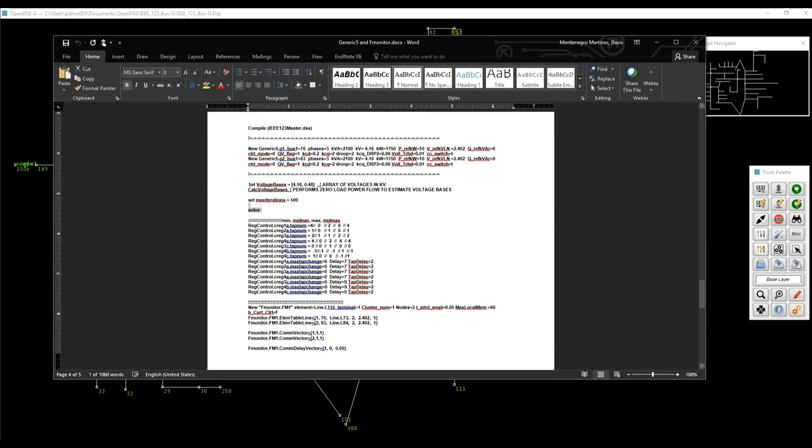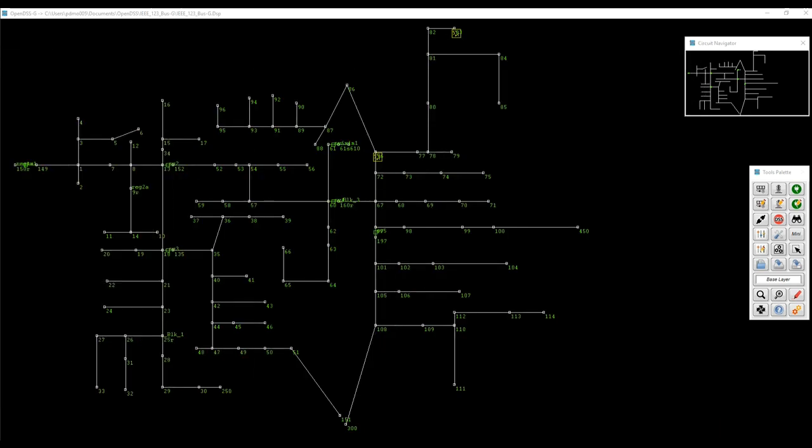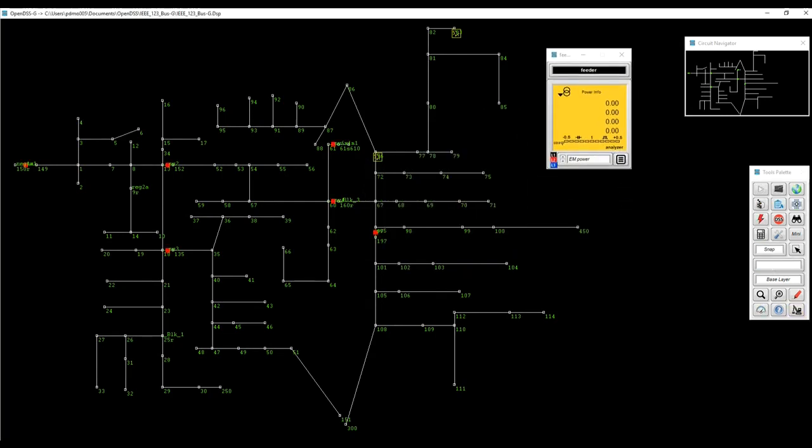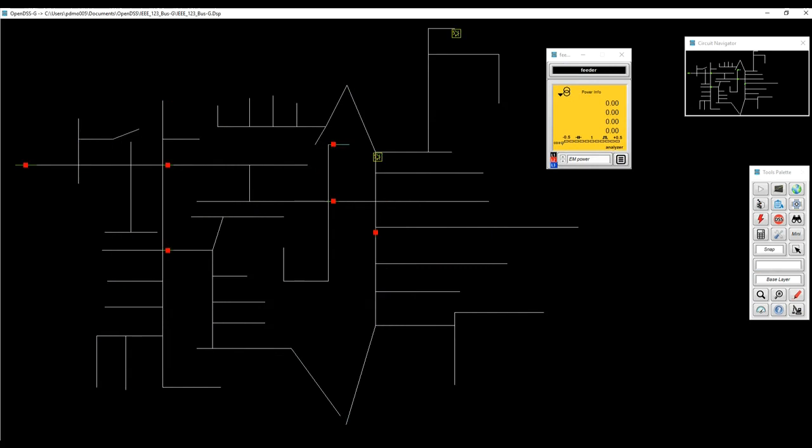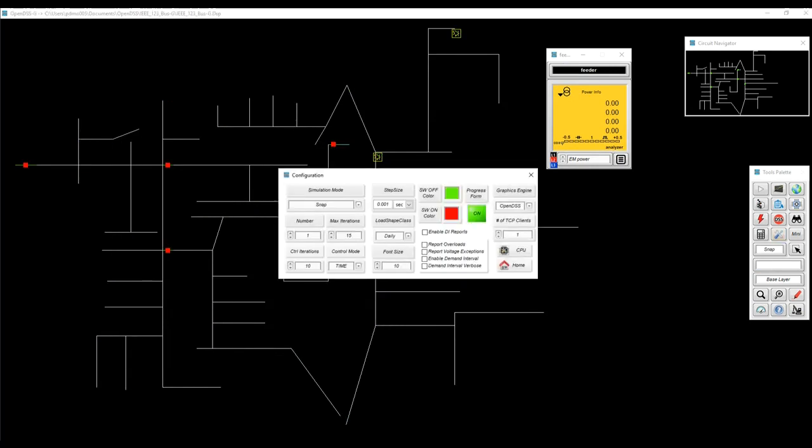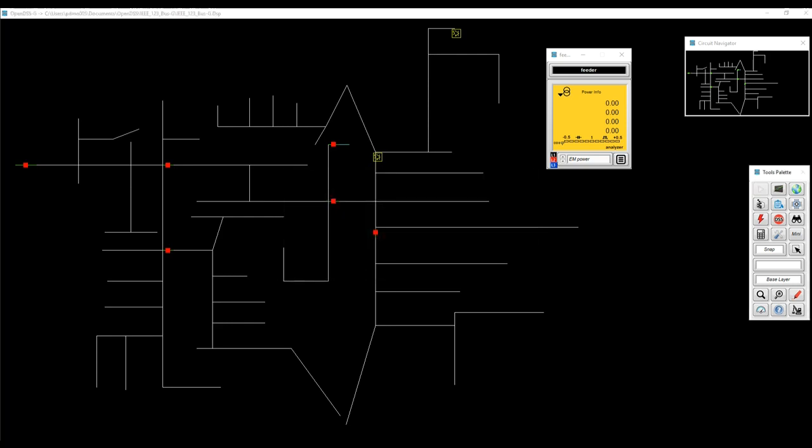Next step is going to be to set max iterations 500 and then make a solution snap mode. That's what we're going to do. So I'm going to enable the simulator palette. I already have energy meter at the feeder head. I'm going to remove the names just to have a clearer visualization. I'm going to set the max iteration 500. I'm going to do the same with the control max iterations just in case.